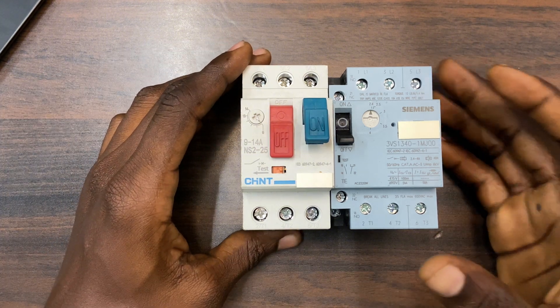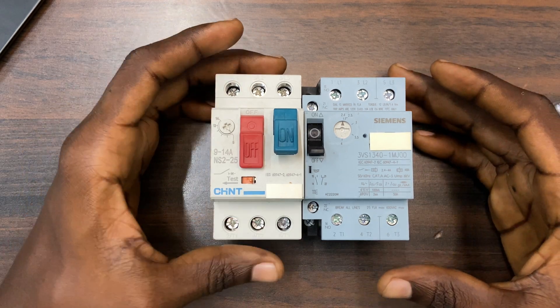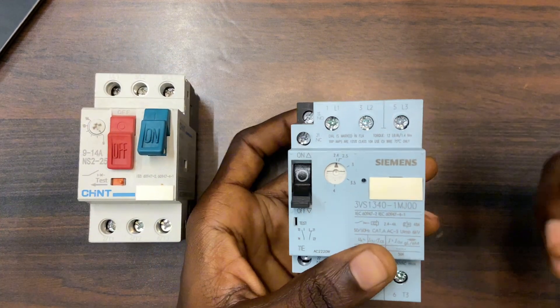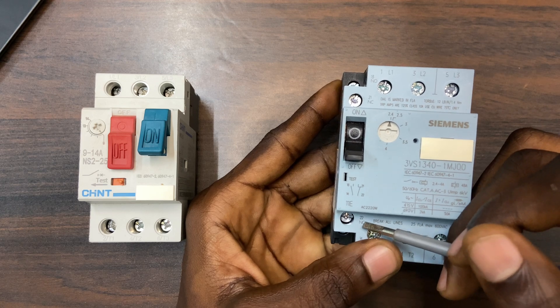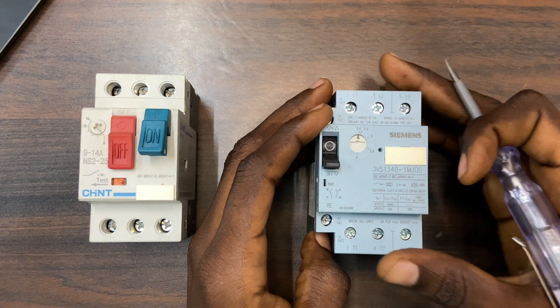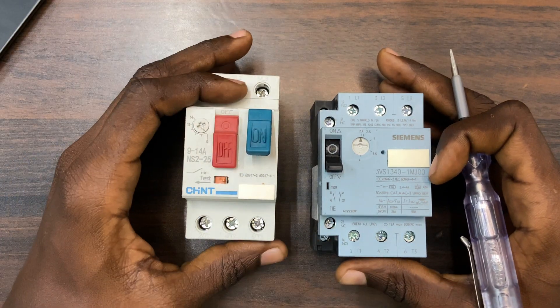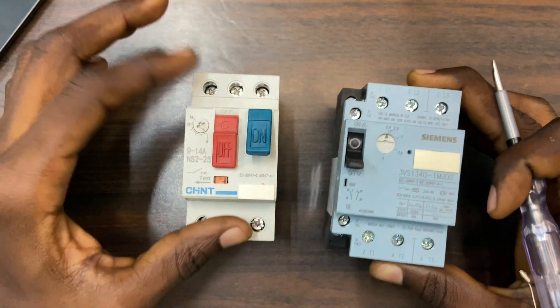I just call it motor protector, motor breaker, and all that, but the actual name is MPCB — Motor Protection Circuit Breaker. You can also call it any other name that you know. You can see that this Siemens motor protector has extra terminals here — the power terminals 1, 2, 3 on each side — and there are also auxiliary terminals: 21 and 22 which is normally closed, and 13 and 14 which is normally open. These terminals can be used for trip indications. With the Chint we also have these terminals, but you cannot see them yet.